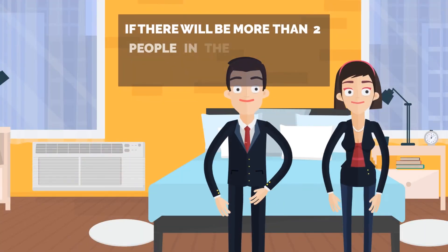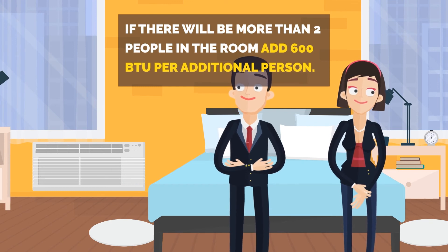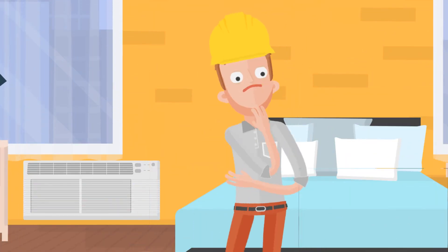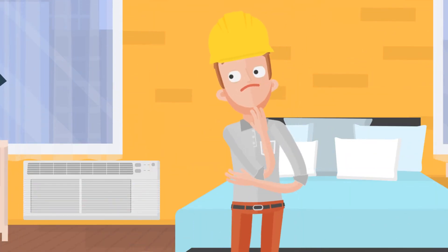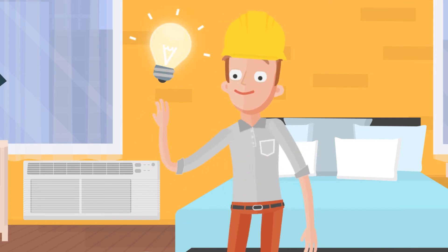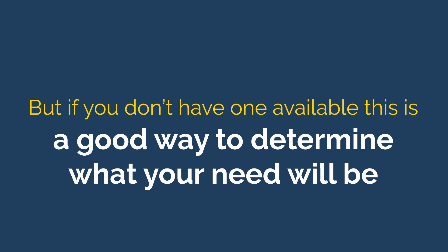If there will be more than 2 people in the room, add 600 BTU per additional person. It is always better to have a mechanical engineer make the calculations for you whenever possible. But if you don't have one available, this is a good way to determine what your need will be.